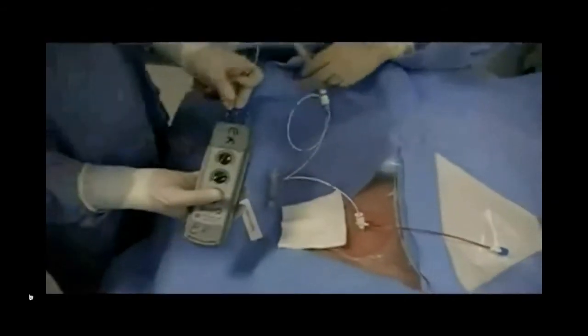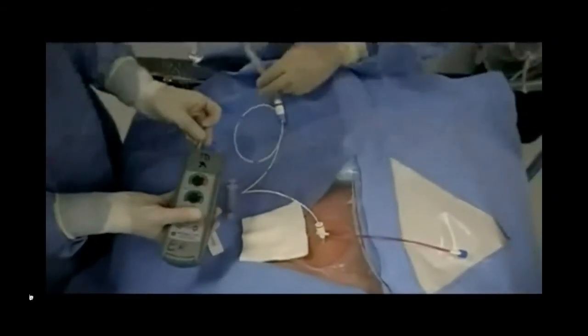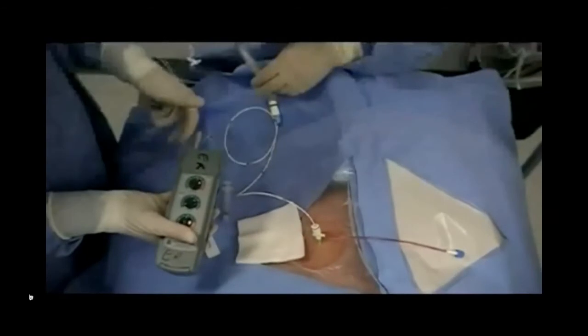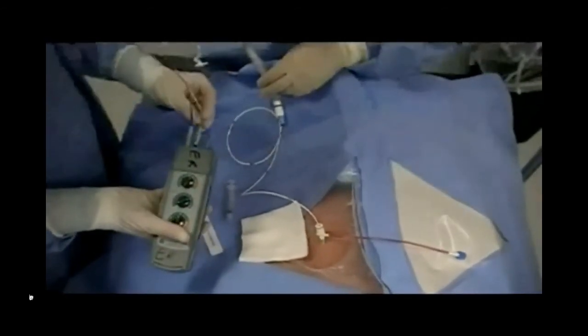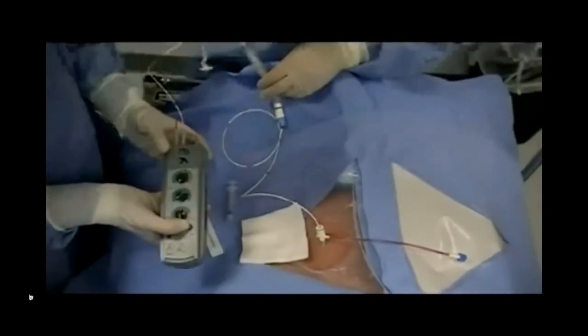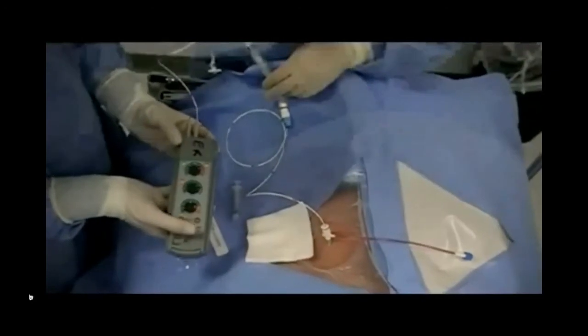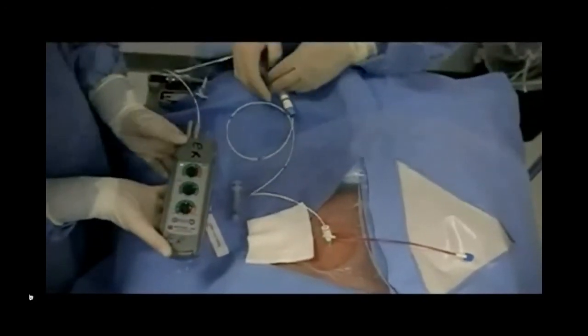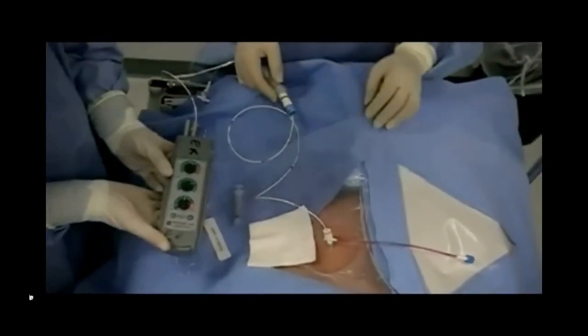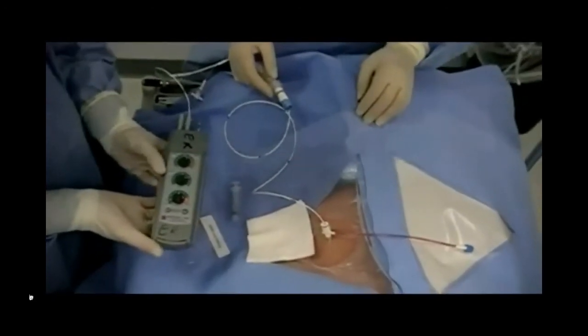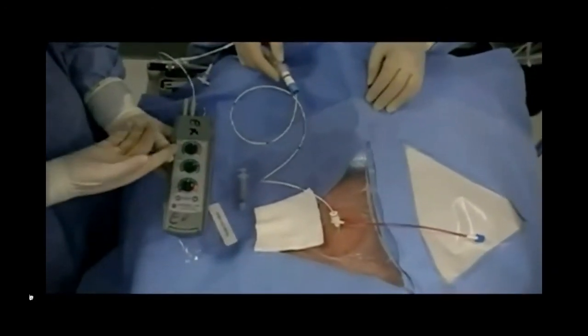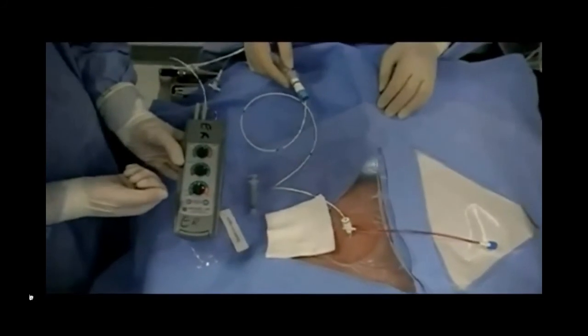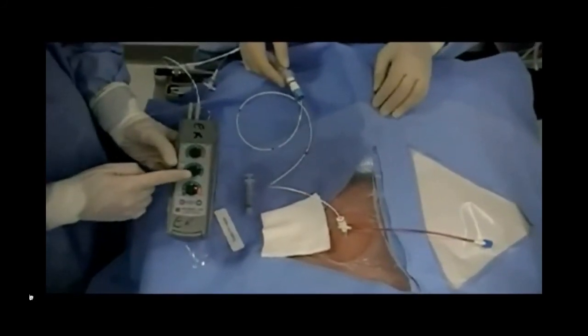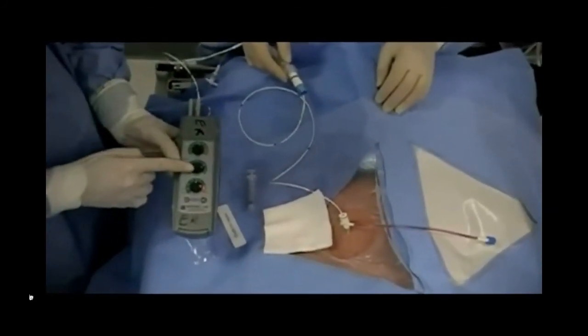Ports should be inserted positive to positive and negative to negative. At this time, the pacing box can be turned on. The rate should be at least as high or higher than the patient's innate rate. As the catheter is advanced, watch the monitor for pacer spikes.